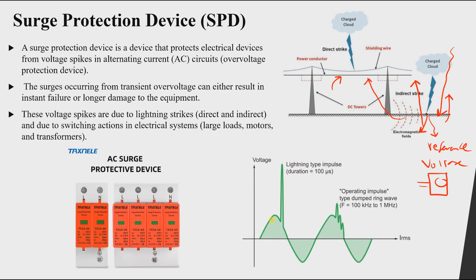Looking at waveforms — for a normal 220V phase voltage, a lightning strike causes a very large overshoot in voltage for a very short time. The operating impulse due to switching actions produces a smaller impulse. The difference in magnitude means we have different types of SPDs: one for lightning strikes and one for switching actions, each with their own waveform.